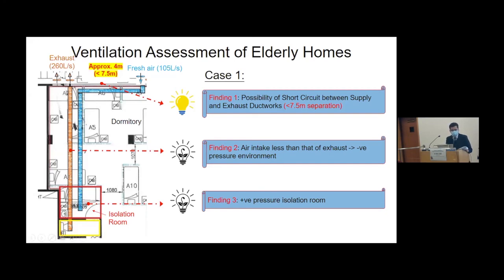This essentially created a negative pressure environment inside the dormitory. Fresh air was being pulled in from a dirty light well where it was suspected to have drainage leakage. As a result, a foul smell was observed inside the dormitory. In addition, only fresh air supply with no exhaust ductwork was observed in the designated isolation rooms, which is right here at the bottom left. This created a positive pressure environment inside the isolation room.